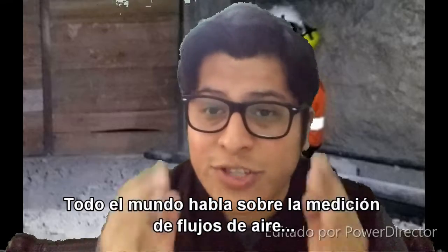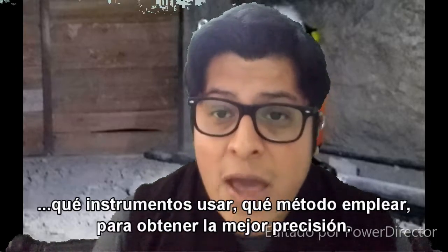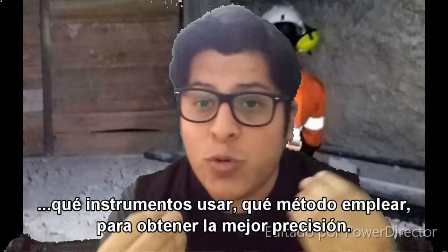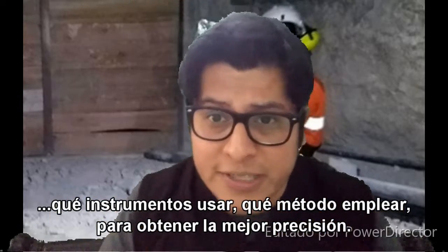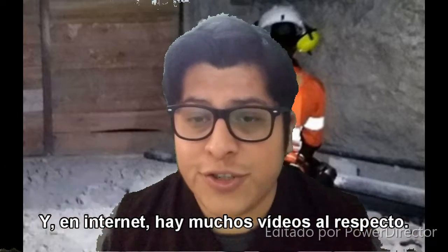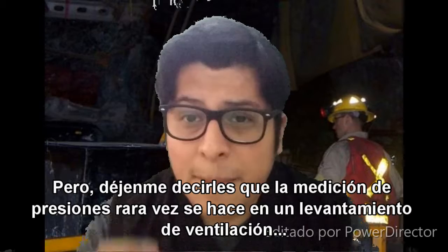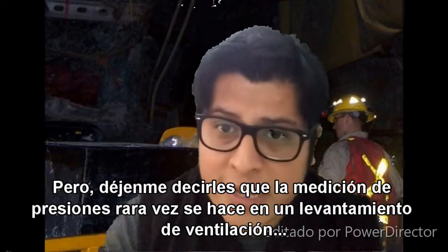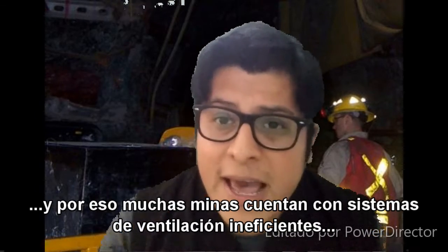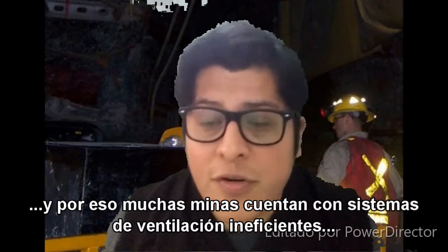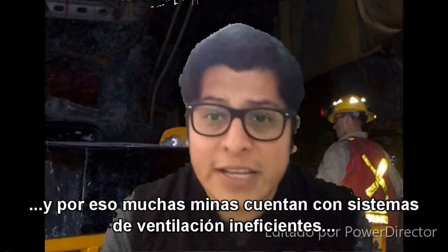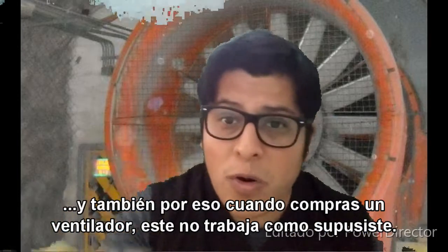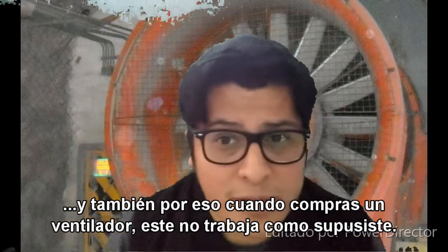Everyone discusses how to take airflow measurements, what instruments to use, what methodology to employ in order to achieve the greatest repeatable accuracy. And there are different videos on the internet that show this. But let me tell you that pressure measurements are rarely done in a mine ventilation survey. And that's why most mines run inefficient ventilation systems. And that's why when you buy a fan, it doesn't work the way you suppose it will.